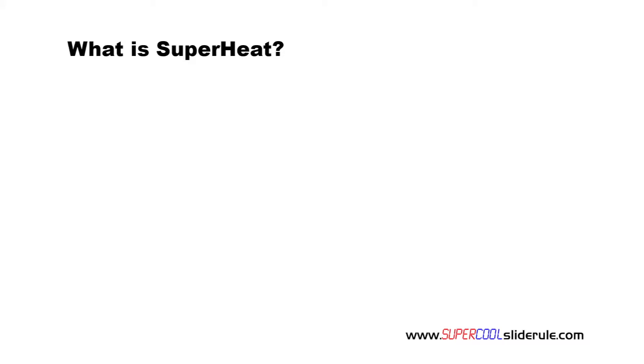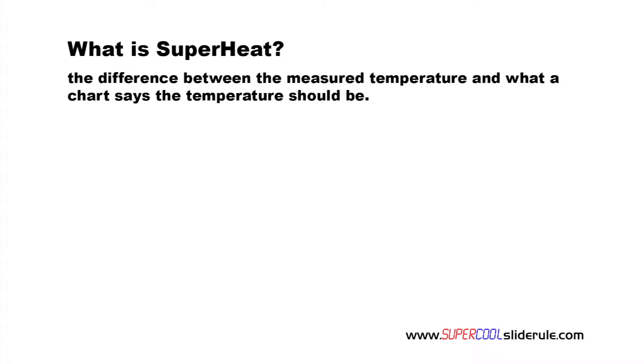All refrigerants have a relationship for pressure and temperature, so at any given pressure there should be a corresponding temperature. Superheat is simply the difference between the measured temperature and what the chart says the temperature should be.